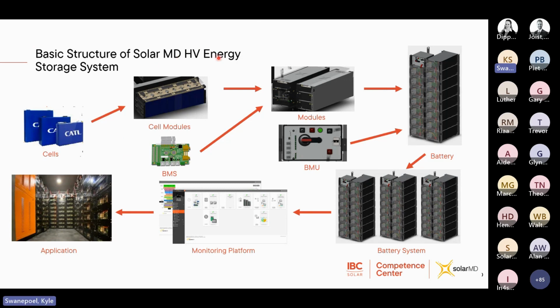Just the basic structure of the energy storage system. For the HV batteries, the cells are CATL cells. It's a 280 amp hour cell, nominal voltage of 3.2 volts. So there's 8 cells that get put into a cell module, and 2 cell modules with a single BMS will form a battery module. As you can see, there's the 2 cell modules over there, and you have the BMS. And then to include a BMU, which is the battery management unit. This is where all your protection lies. This is where the logic of the battery lies. And pairing these 2 together, you're going to get yourself a SolarMD HV battery solution, which will look something very similar to this.